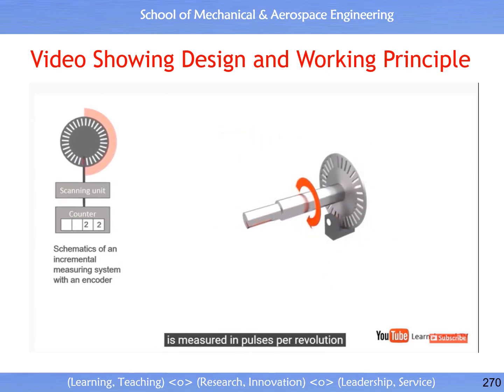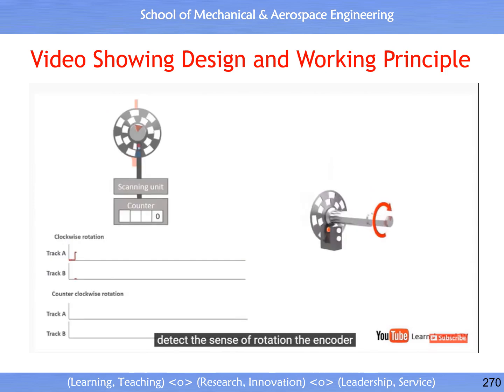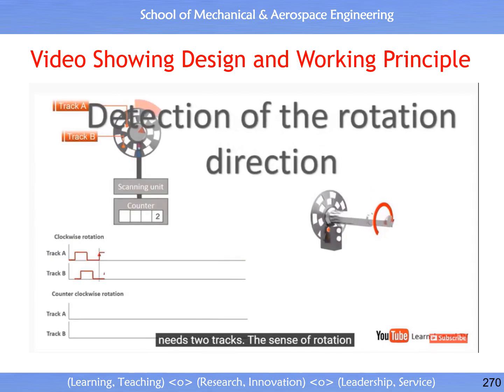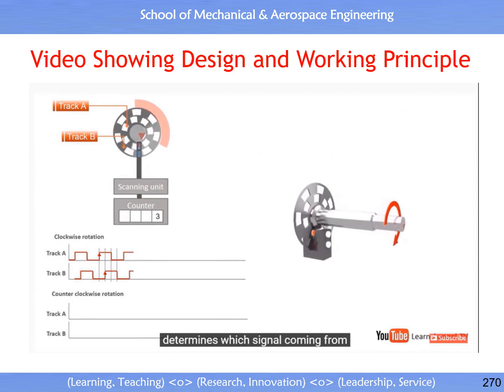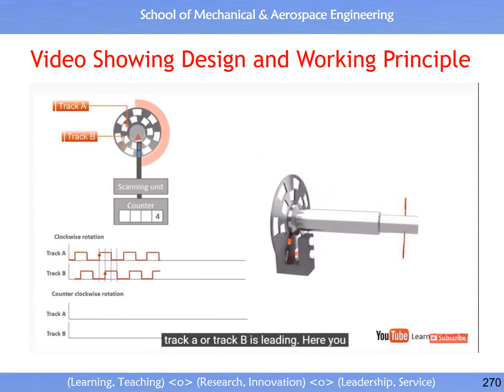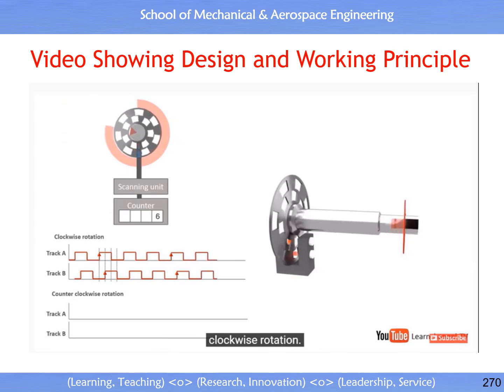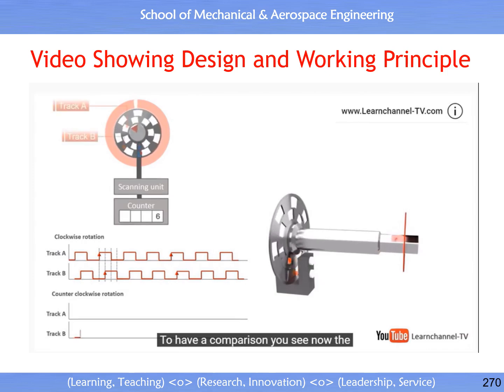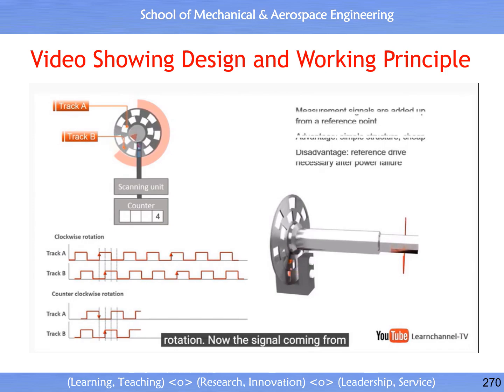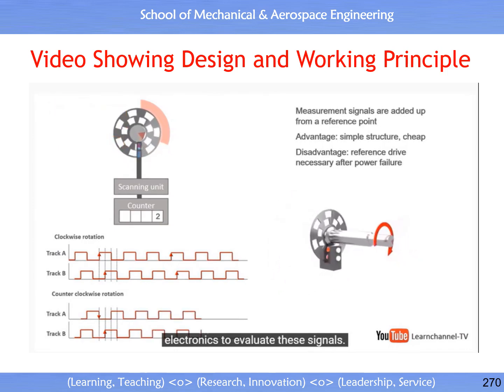The output is measured in pulses per revolution, which can be used to determine either the position or the rotational speed. To detect the rotational sense, the encoder needs two tracks. The sense of rotation determines which signal coming from track A or track B is leading. Here, you can see the signal form coming from clockwise rotation. To have a comparison, you see now the signal form coming from counterclockwise rotation. Now the signal coming from track B is leading. It is now up to the electronics to evaluate these signals.